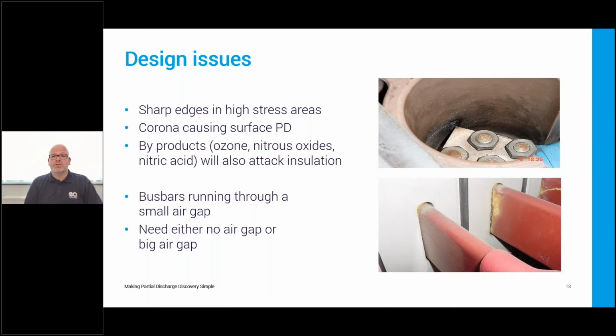And on the bottom picture, you can see where some insulated bus bars are running through this panel with a very tight air gap, and PD activity has developed around that entry point. You can see on the picture there the physical damage to the insulation.